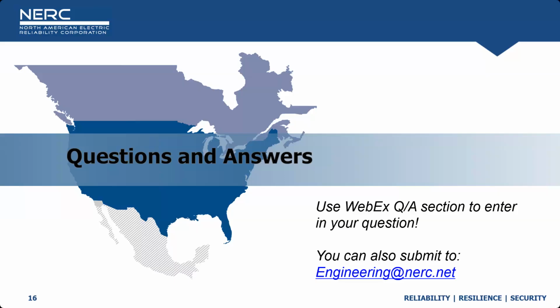Yeah, this is fantastic. I was just in a presentation from Dominion this week, and they were really trying to highlight and emphasize that when you have an event on your system, and maybe you see data centers or other large loads have a customer-initiated load reduction, maybe following a normally cleared fault, it is -- I think they used the word impossible -- you cannot accurately determine what transpired and what caused that reduction unless you have some high-speed recording.